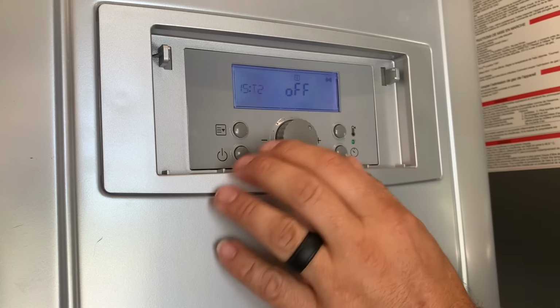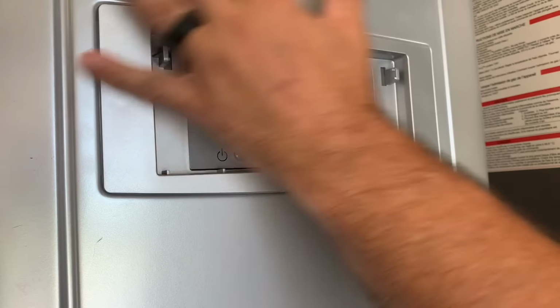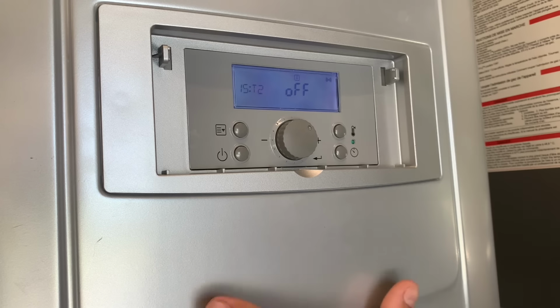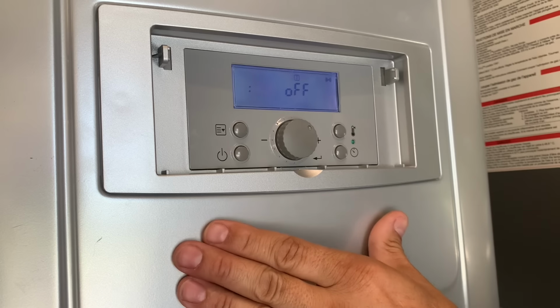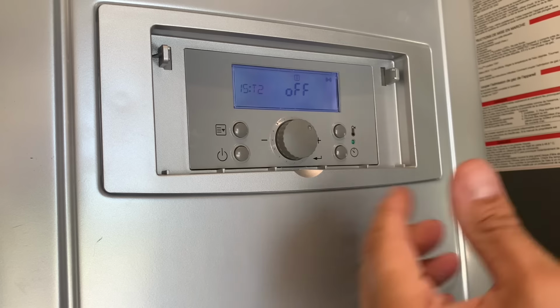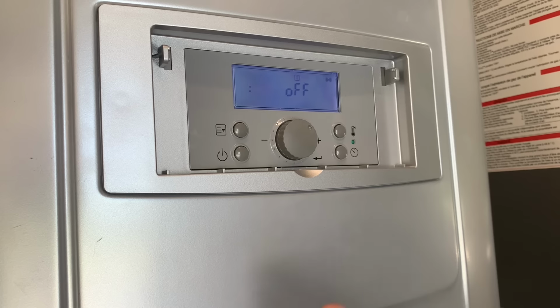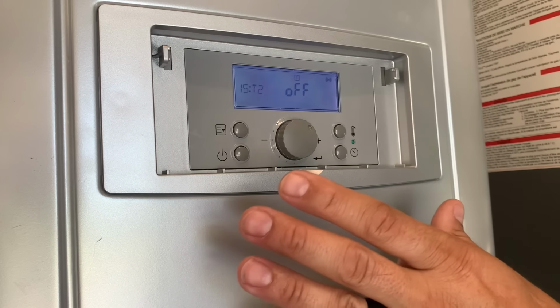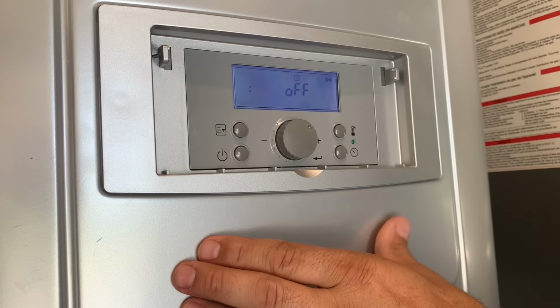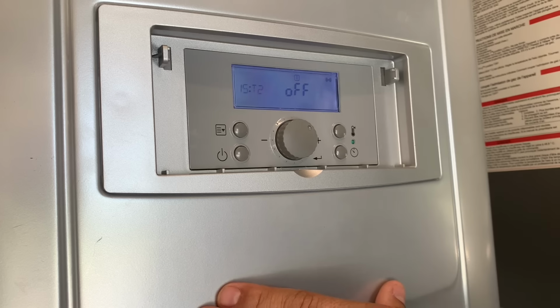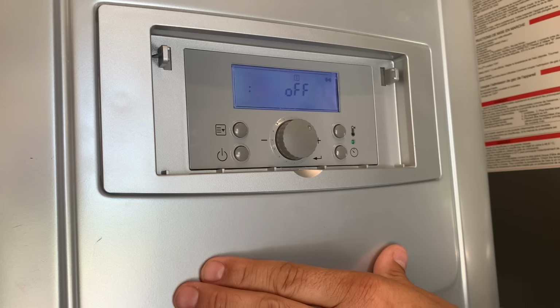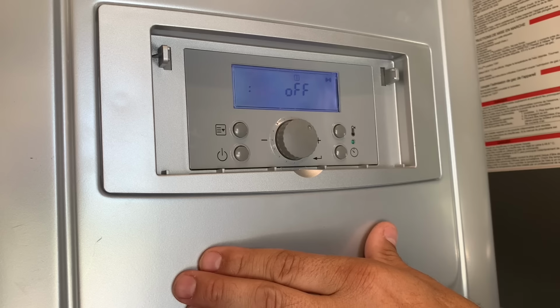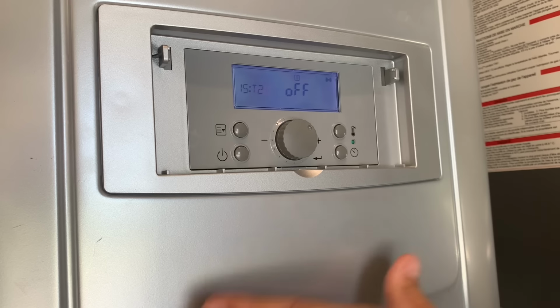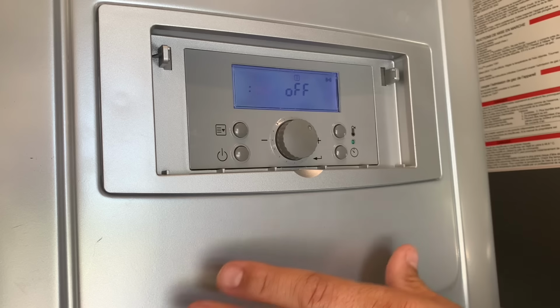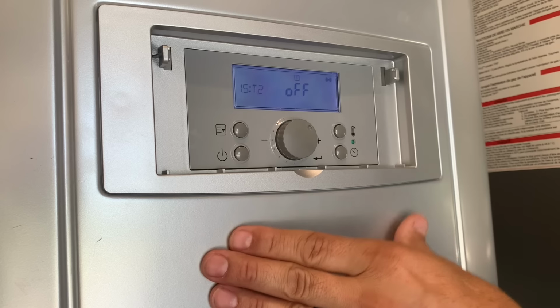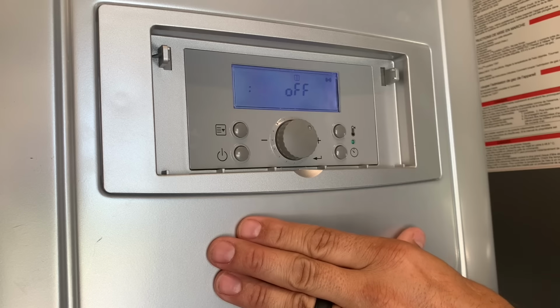And here's the deal with the external recirculation pump. You might be asking, well, if we have one internally, why would we need one externally? If you're using an external pump, it is because you're requiring more power on your circulation system, meaning you've got longer distances. We're limited on the feet limit listed in the use and care manual of about 200 feet of total half-inch pipe and I think 500 on 3/4. Now, if you need to circulate through more than that and you're using the internal pump, it is likely that you may start to get an overheat code.